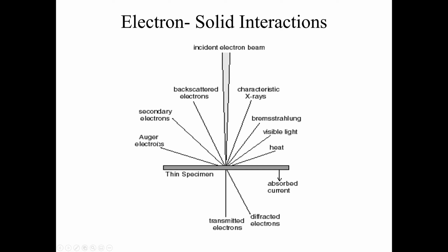In theory, it makes an Auger electron, but due to the fact that it's not a high vacuum system and other technical difficulties, these are not measured by a microscope. If the electron beam has enough energy, it'll go right through the sample, called a transmitted electron, a TEM. And sometimes the electron gets diffracted, so you can sort of do an XRD inside the instrument.